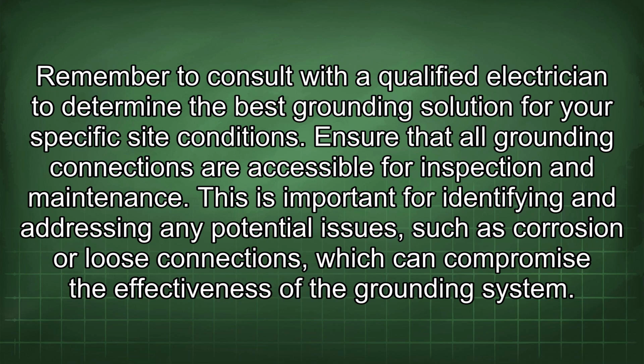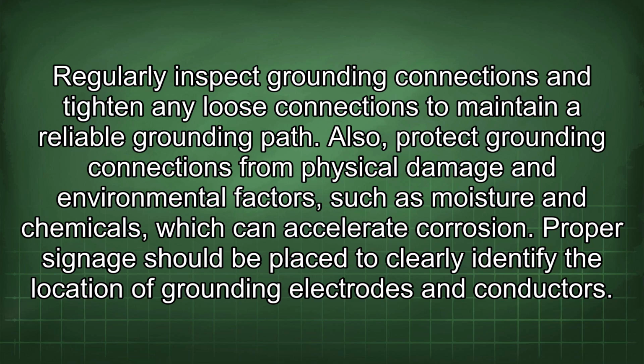This is important for identifying and addressing any potential issues, such as corrosion or loose connections, which can compromise the effectiveness of the grounding system. Regularly inspect grounding connections and tighten any loose connections to maintain a reliable grounding path. Also, protect grounding connections from physical damage and environmental factors, such as moisture and chemicals, which can accelerate corrosion.